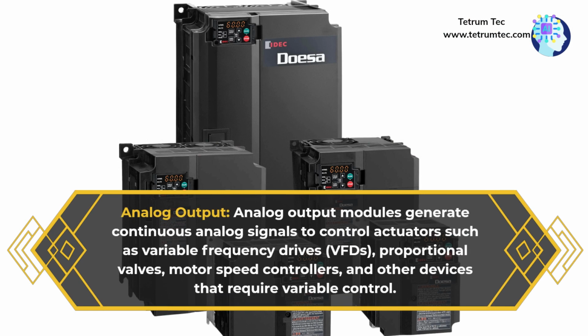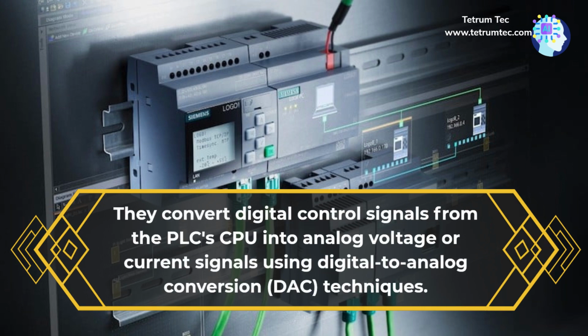Analog output. Analog output modules generate continuous analog signals to control actuators such as variable frequency drives, VFDs, proportional valves, motor speed controllers, and other devices that require variable control. They convert digital control signals from the PLC's CPU into analog voltage or current signals using digital to analog conversion (DAC) techniques.